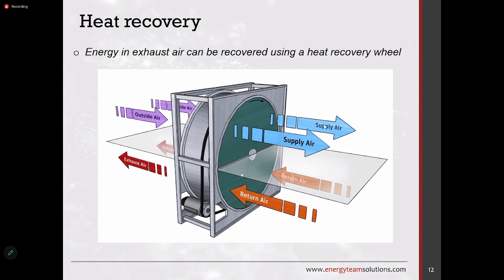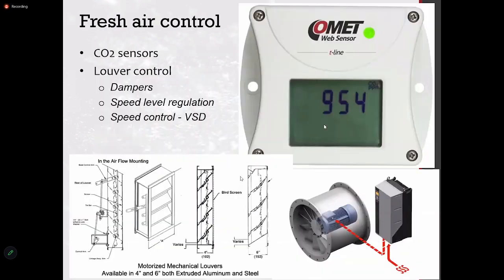So this unit is actually transferring whatever cool is available to the supply side. This is very much used in India, even for default air conditioning systems, they install this and make a lot of savings through the exhaust and supply air. Yeah, so this control part is there, what we discussed. There are CO2 sensors and you have air dampers to actually control the air level coming in.